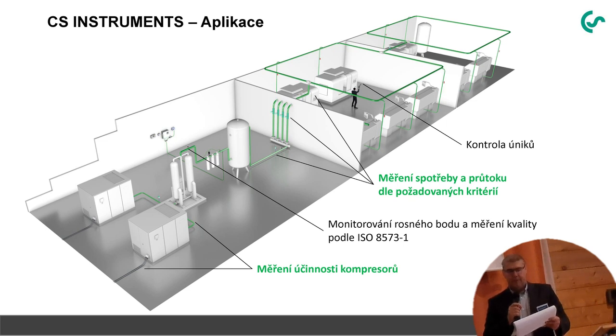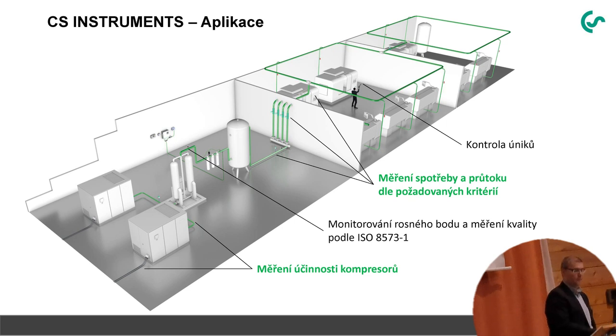Next step, we have the dew point monitoring and quality measurement. After the dryer, usually you have compressed air drying systems. Then we can also measure the consumption and flow of the demand profile, how much is needed in the factory. And last but not least, we have the leakage management.